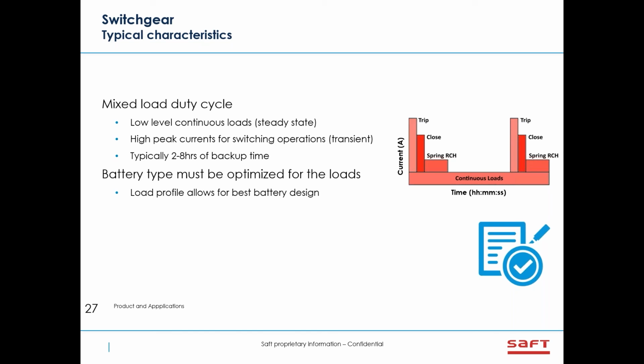There's one mistake that often gets made. Somebody says, hey, I have a 300 amp hour lead acid battery in my switch yard, I need a 300 amp hour lithium ion battery. But that's not a good way to size lithium, because typically the lead acid has to be oversized to handle the trip loads and the peak currents, where lithium can handle those loads very well. It's very good at power. Even our energy cell is much better than a lead acid cell at peak loads. So we often can have a smaller amp hour battery do the same job that a bigger lead acid battery would. So when I size a battery, I really like to get this type of information from the customer.